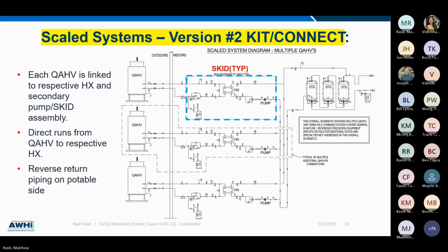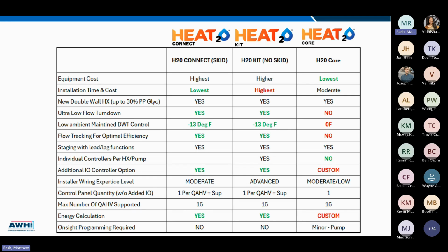And then there's also an option that you can harness the information from the skids or from the kits with regard to the flow meters and the temperature sensors to do all that COP monitoring and demand response functions that are built into that. And I'll show some of that in a minute. So again, this Connect option, pre-packaged, pre-piped, taking all of that out of the hands of the contractor, minimizing problems in the field. Again, it's going to include that 10-gallon buffer tank and expansion tank. This is the only option that has those included, pre-piped. All the other options, the expansion tank and buffer tank, are field provided.